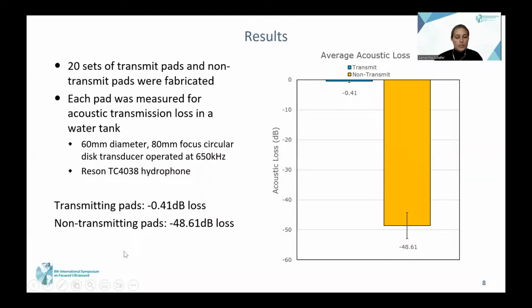So after production, each pad is individually tested for its efficacy in both transmitting and blocking ultrasound. Again, the design goal for the acoustic attenuation or blocking pad was -40 dB, which is a factor of 10,000 in intensity, and is close to 0 dB for the transmitting pad. 20 sets of transmit pads and non-transmit pads were fabricated and tested. We tested them in a water tank for acoustic transmission loss. We used a 60 millimeter diameter, 80 millimeter focus circular disc transducer operated at 650 kilohertz and a standard Reson hydrophone.